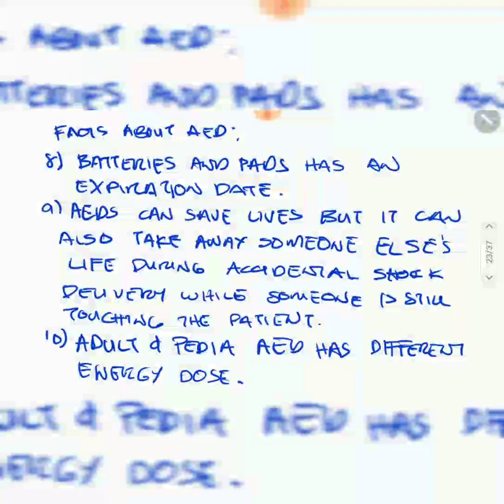Then some AEDs will deliver shock right after rhythm analysis. Do not touch the patient, be careful always, and be familiar with the functions of your AED. Batteries and pads of an AED have an expiration date, so please always check on that. AEDs can save lives, but they can also take away someone else's life during an accidental shock delivered while someone is still touching the patient.